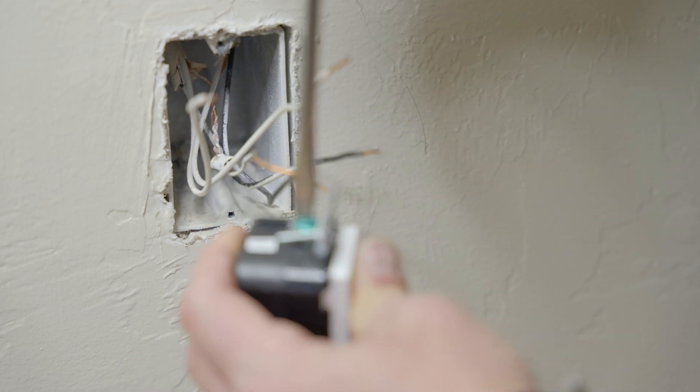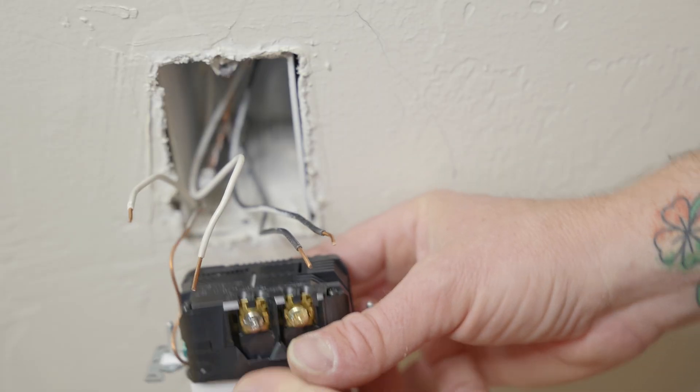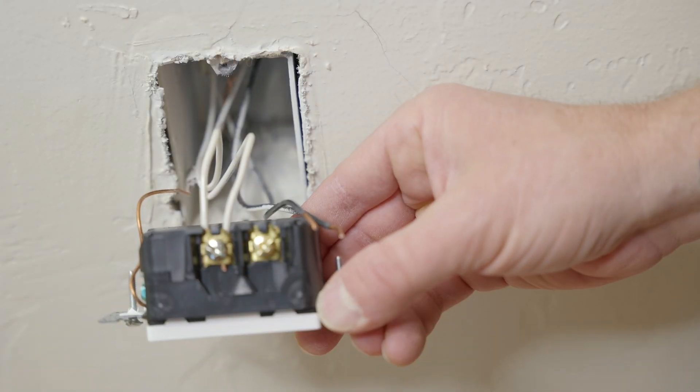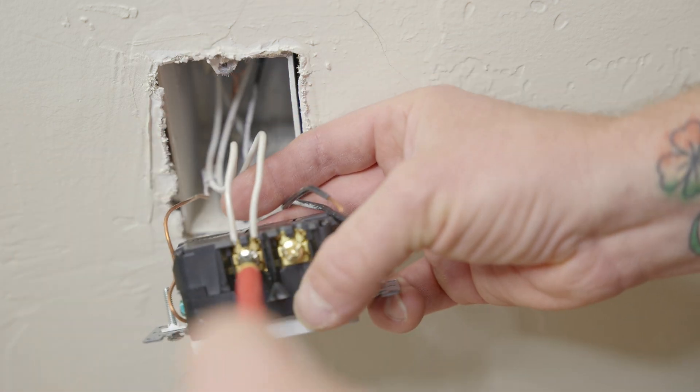Of course first we want to hook our ground onto the green lug as always in a clockwise rotation. We'll hook up our two white neutral wires and they will both go in between two plates. And then we will carefully lock down the terminal screw and then give that a good tighten.